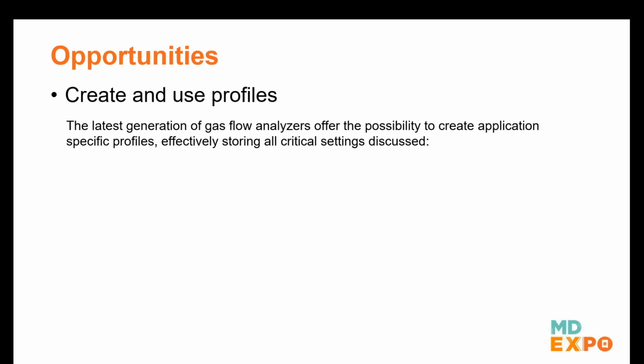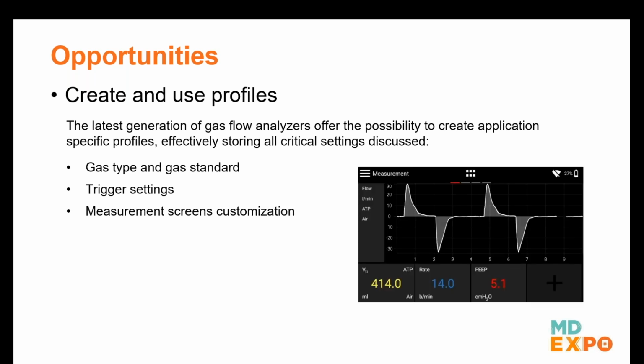So what are the opportunities offered by all these settings changes that we talked about? One thing: if you have a gas flow analyzer that features profiles, then it's highly recommended to use profiles. Modern gas flow analyzers let you save all your settings in profiles, so you can load them later on if you come across the same application again. Profiles hold settings like gas type, gas standard, your trigger settings, and all the measurement screen customizations you have made on your gas flow analyzer. That's very convenient because sometimes it takes some time to figure out what my right trigger settings are. I figure out by calling the ventilator manufacturer what gas standard it is using, so I want to make sure that I save that for later on, right?